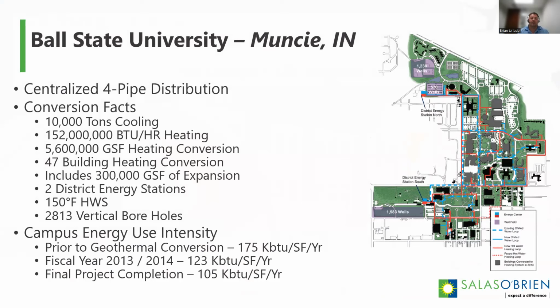It was originally designed for 150-degree hot water to the buildings, because again, most of these buildings are relatively old. They haven't had a lot of envelope upgrades, et cetera. And the facilities people on a lot of these campuses will never believe that you can take these buildings and heat them with 150 or 140-degree water. They're used to running steam, converting that steam to a minimum of 180-degree water. A lot of them are at 200.